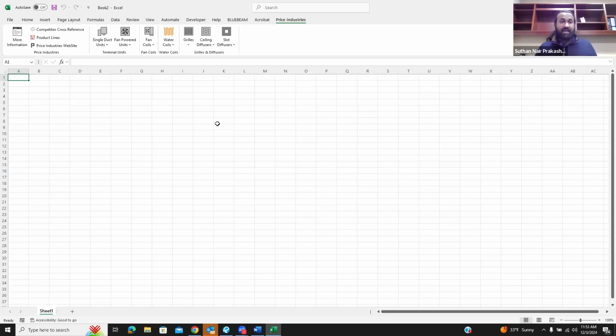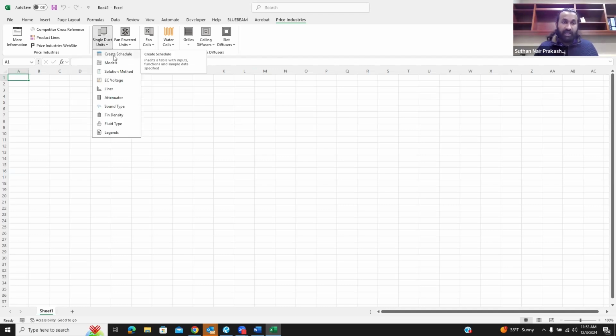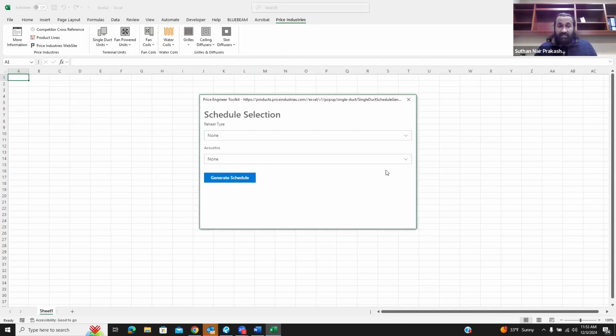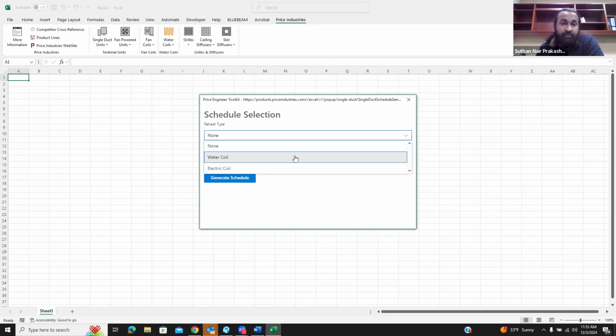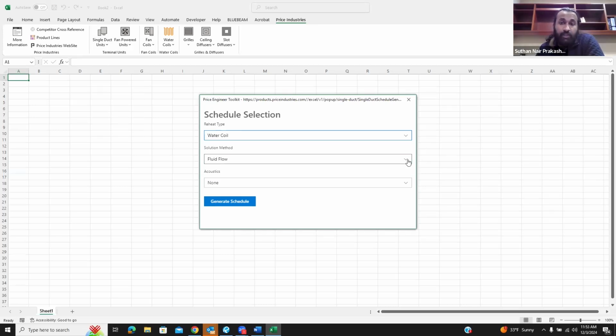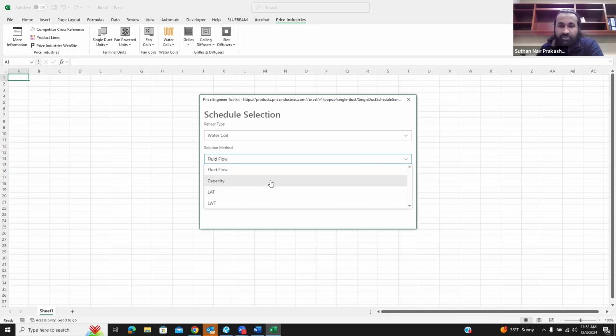So right here, when you have this tool for selecting, for example, we can do a single duct unit for now. When you click on single duct unit and go to create schedule, it's going to ask for two different parameters. The first one is going to be your reheat type, which can either be a water coil or an electric coil. Let's assume I'll do a water coil today. The second thing is the solution method. I know a few people have different types of solution method they want to try to solve with. LAT is usually optimal for occupant thermal comfort, and I think a lot of engineers prefer to go with the capacity. So I would run with the capacity.